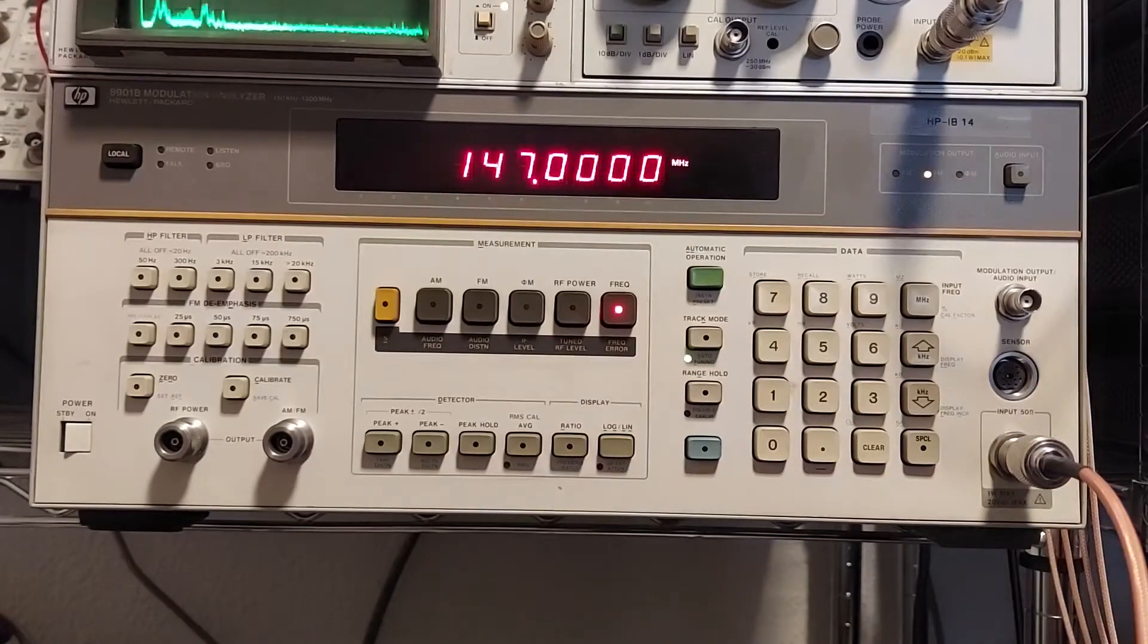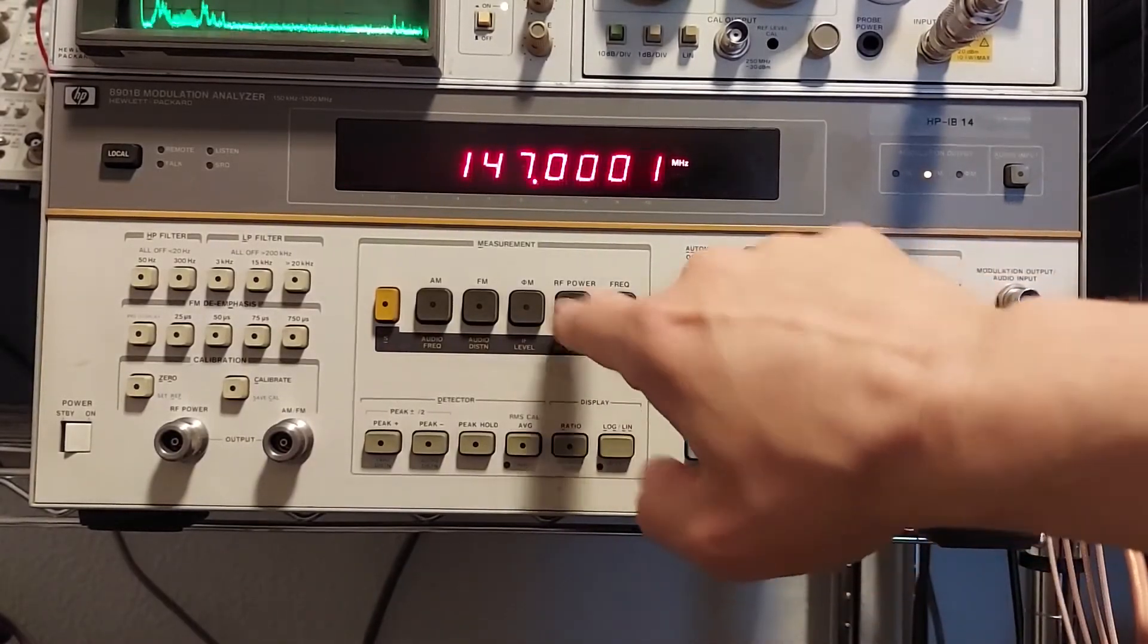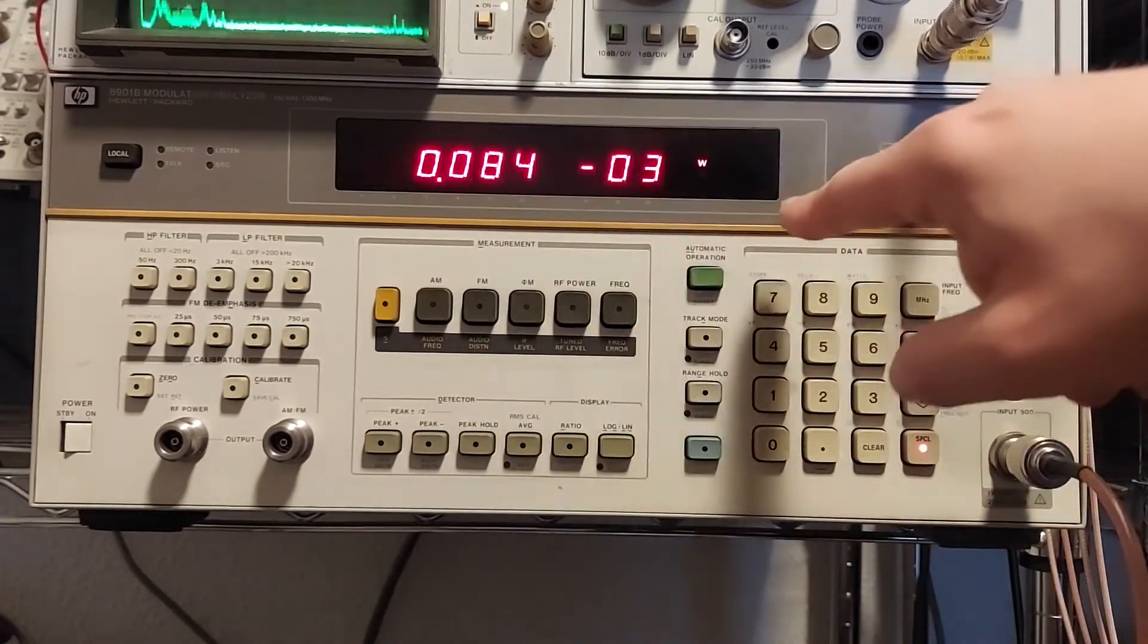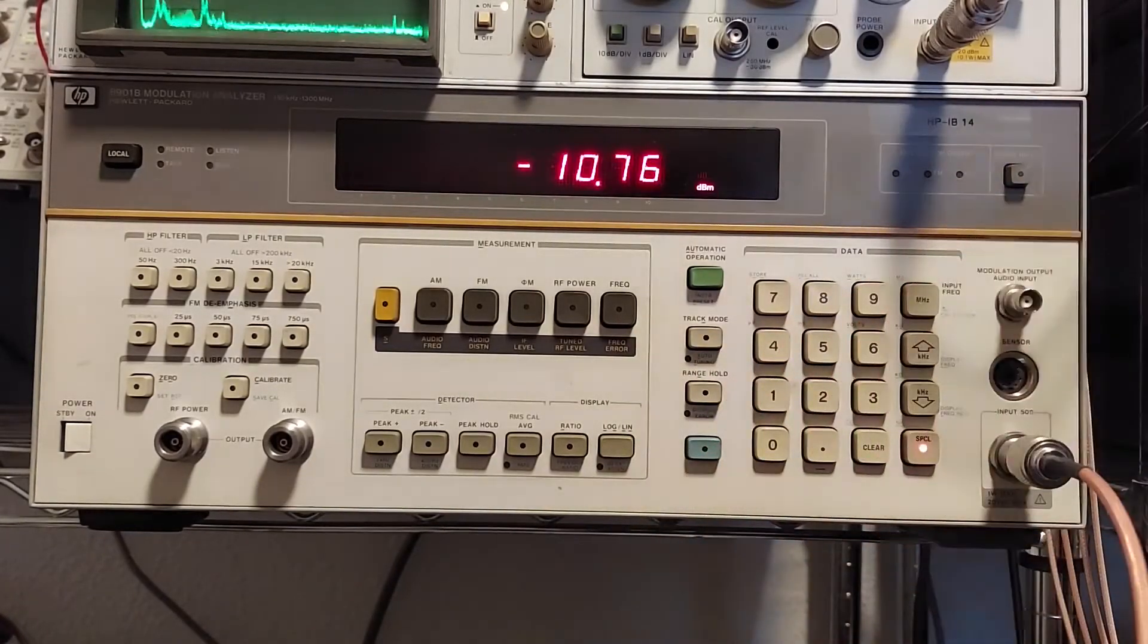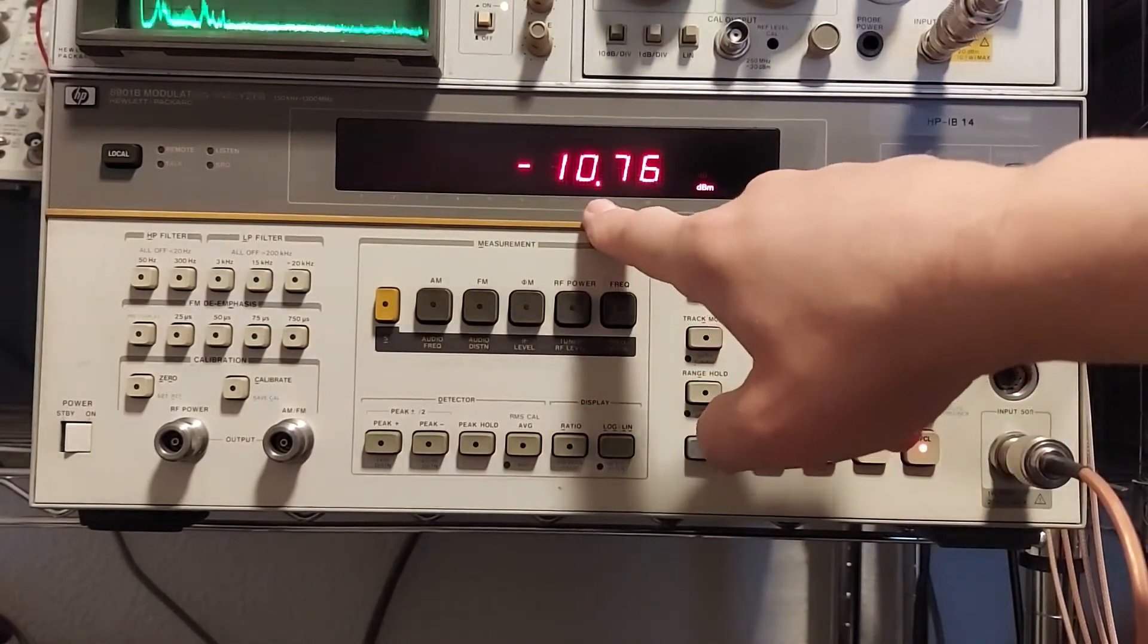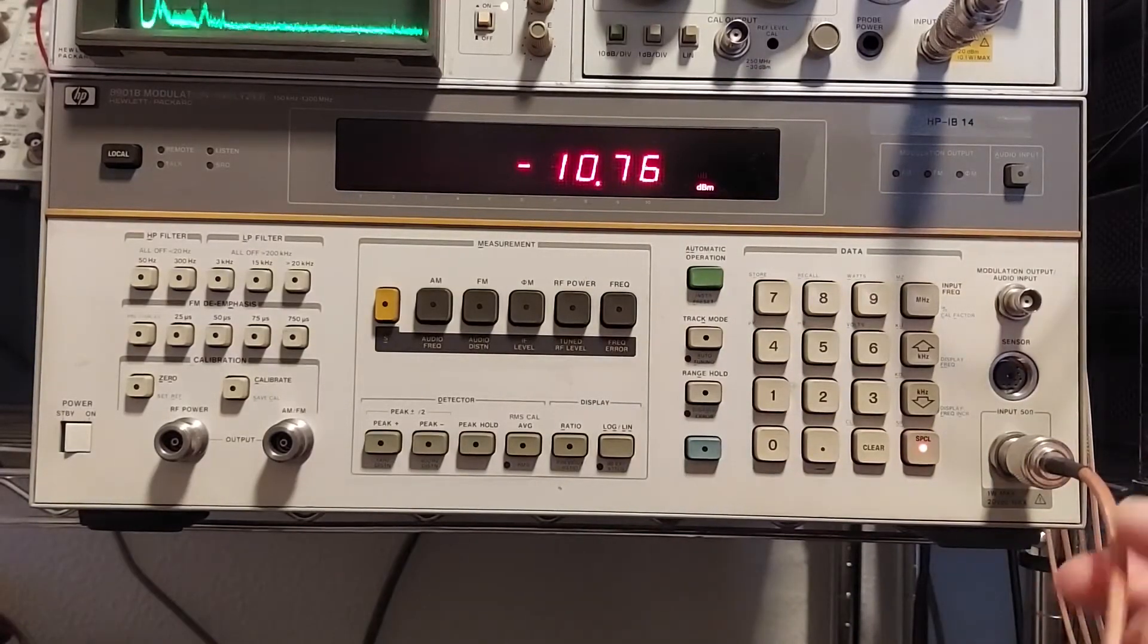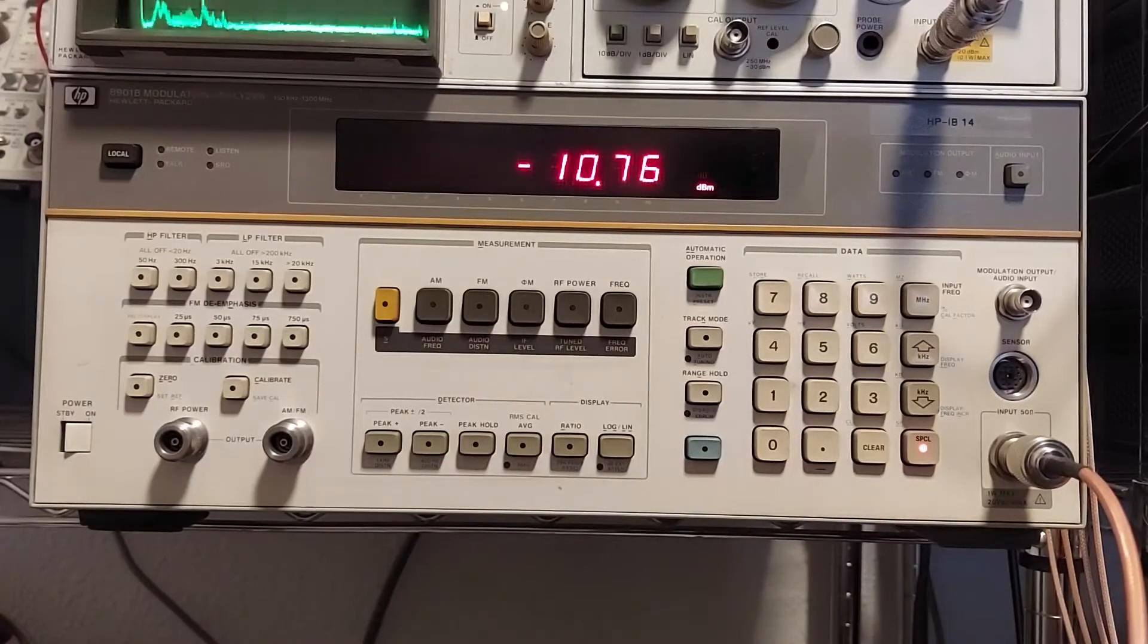The next thing we can do is we can also measure the power level we currently got going into the instrument by pressing power. And initially it comes up in watts, but you can change that by pressing the log button. And now we're showing that the signal going in is about minus 10 dB. There's a little loss here from this cable. It's kind of long and it's got a few connectors in it. So we're getting some insertion loss.